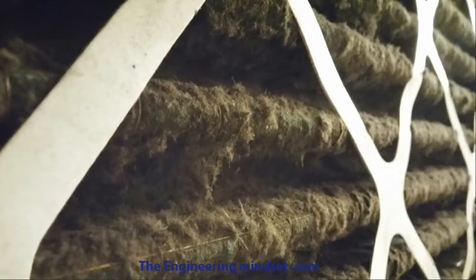When you start to get all this dust accumulating in your ductwork, then the fans need to run a lot harder to get over that pressure drop from the resistance that it causes. If too much dust built up on the motor or some of the mechanical parts, then it could even potentially cause a fire also. Sometimes if you're using some expensive filters, then these pre-filters, primary filters, are placed in front of them to try and reduce the amount of dirt and dust caught by the expensive ones, and that lets them last a bit longer, whereas these primary ones are fairly cheap and they can just be thrown away.